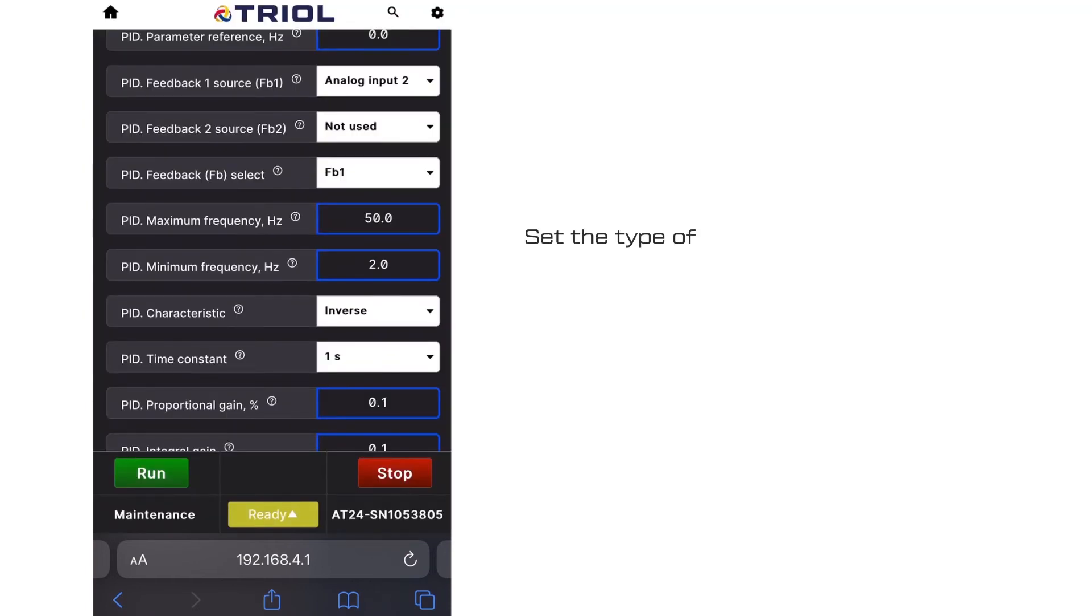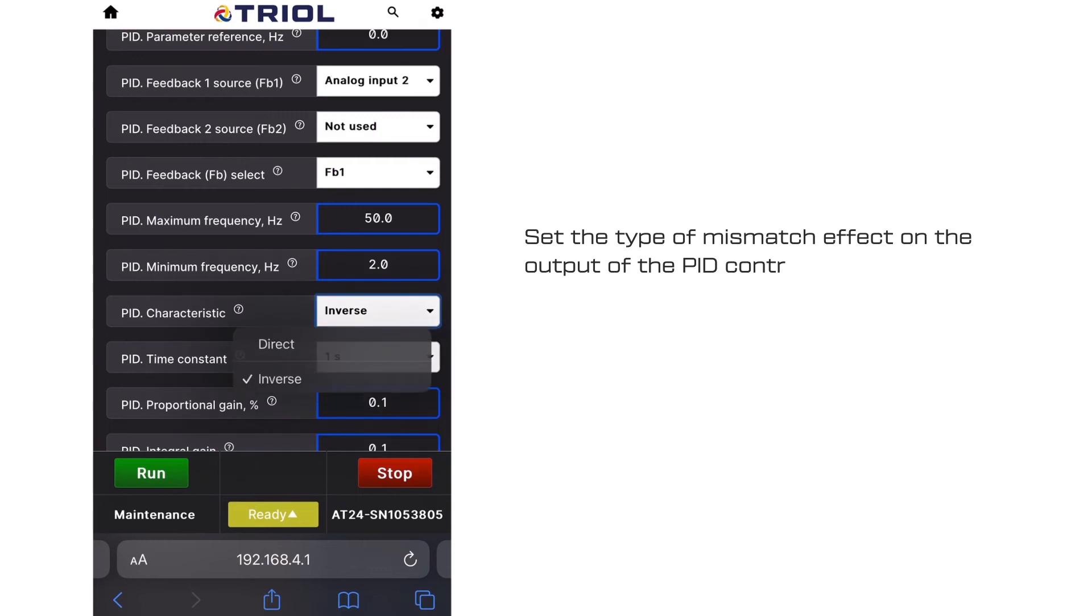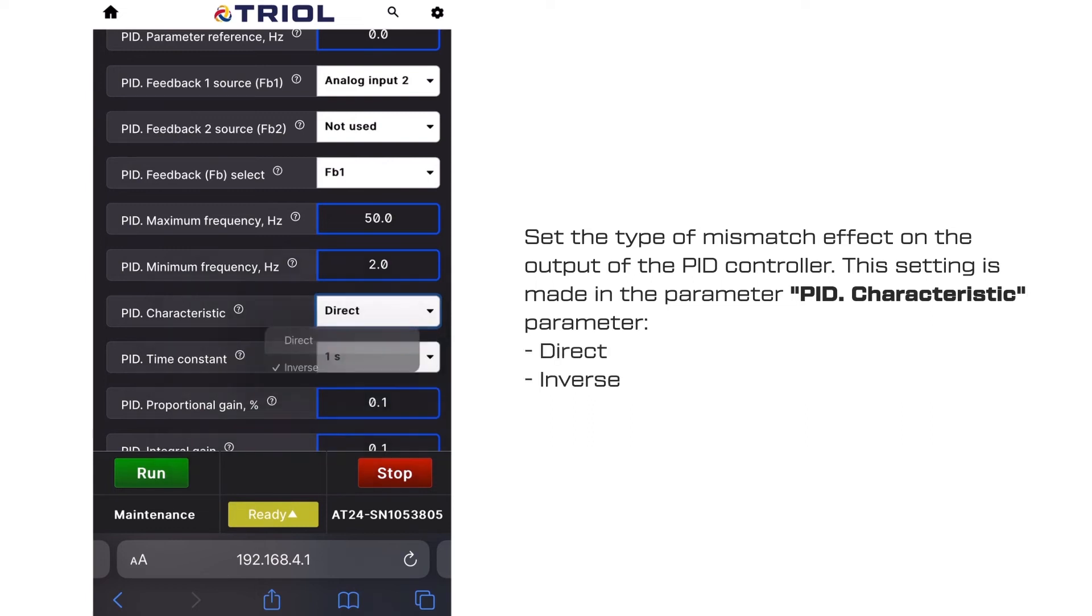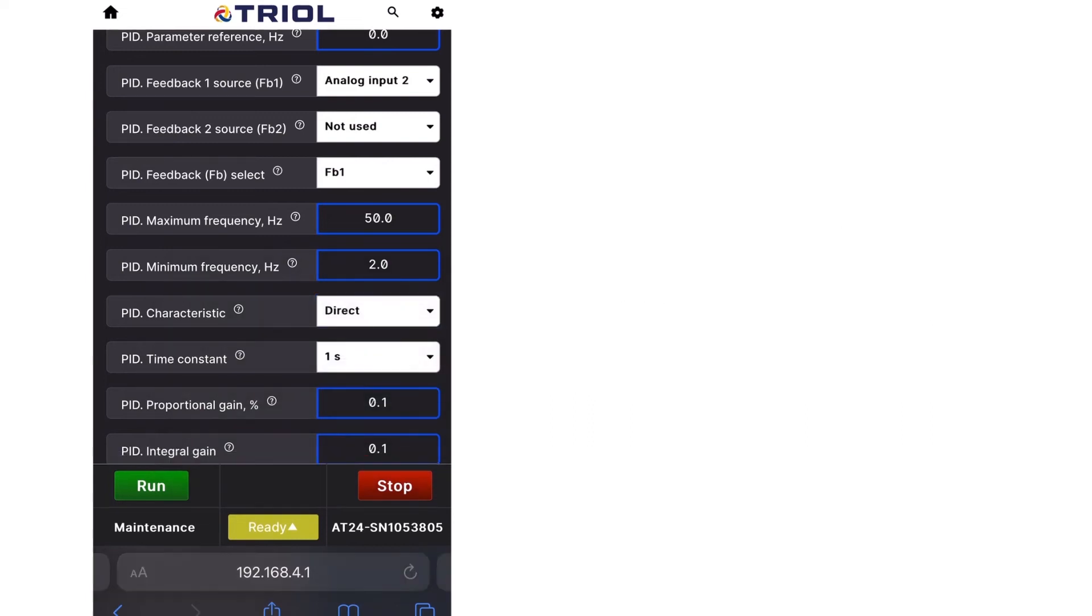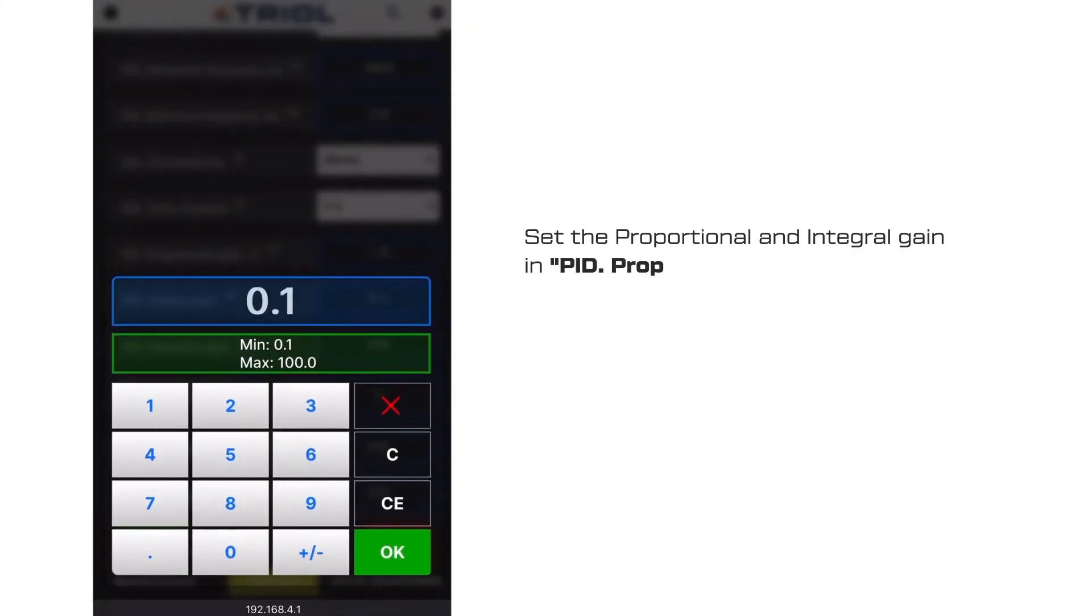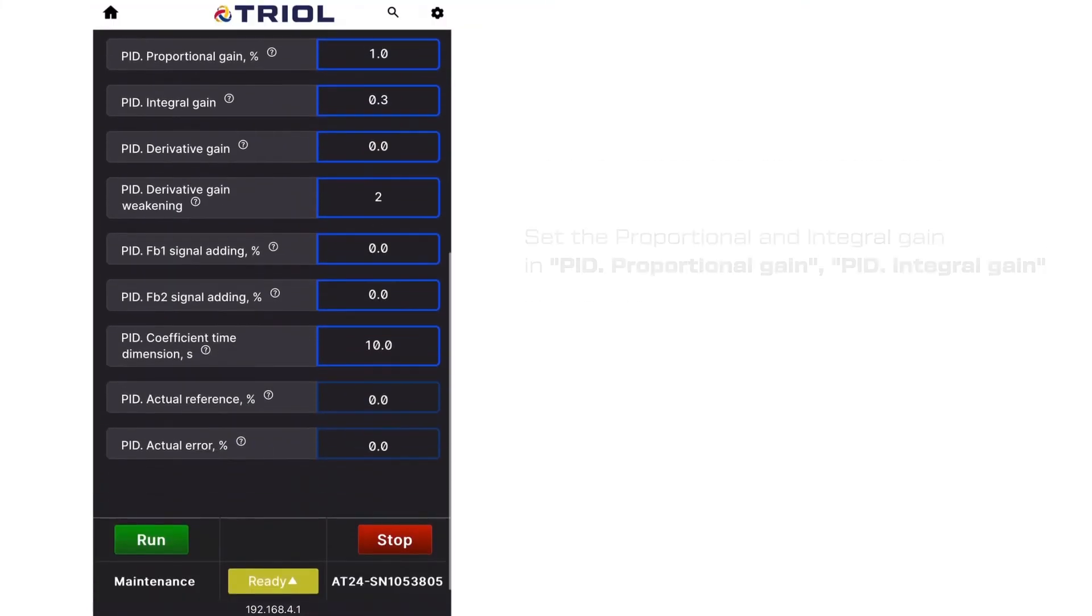Set the type of mismatched effect on the output of the PID controller. This setting is made in the parameter PID characteristic parameter: direct or inverse. Set the proportional and integral gain in the PID proportional gain and PID integral gain.